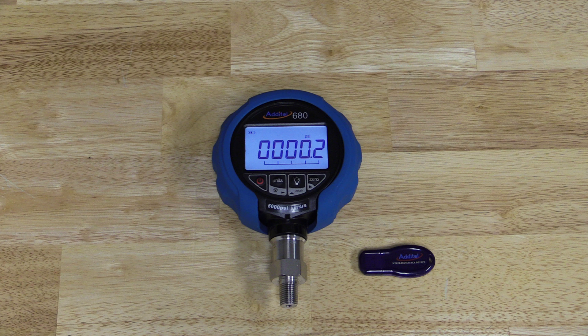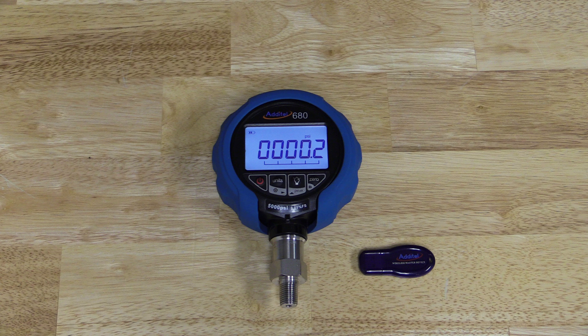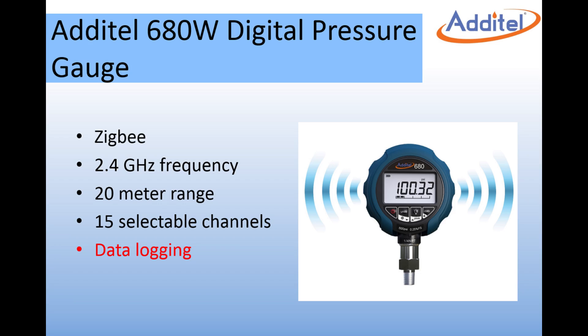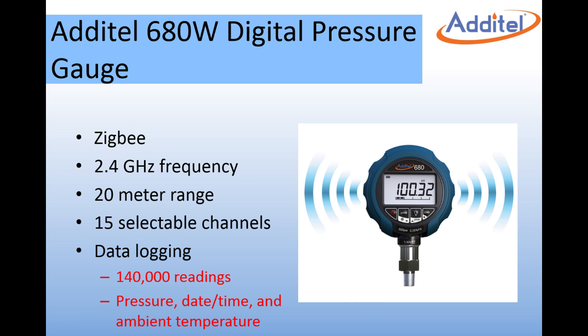The ADT-680W comes with a wireless receiver and works with Additel Land Wireless software which reads up to 20 gauges at once. The ADT-680W also has onboard data logging storage capacity of 140,000 readings. Each reading includes pressure, date, time, and ambient temperature.